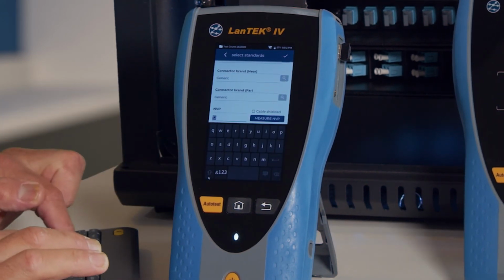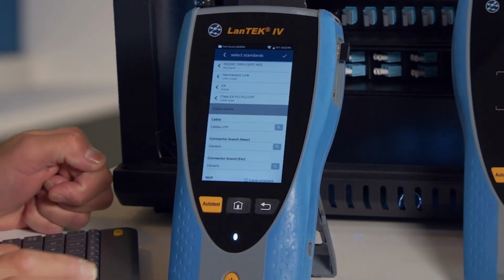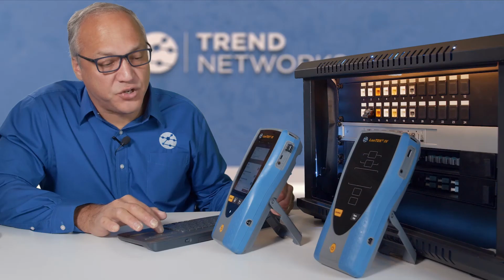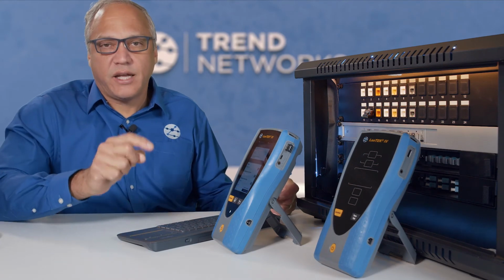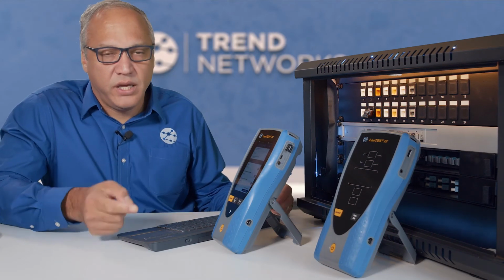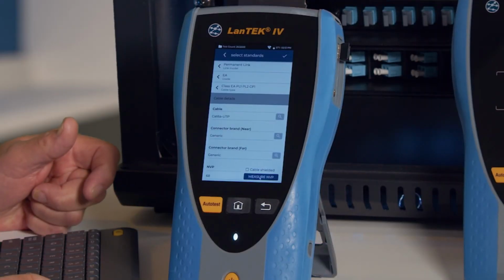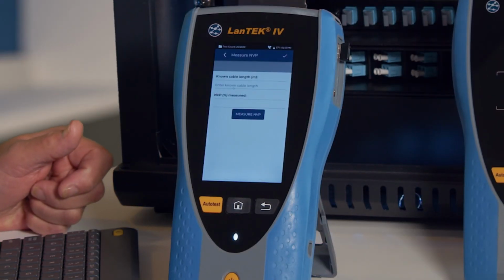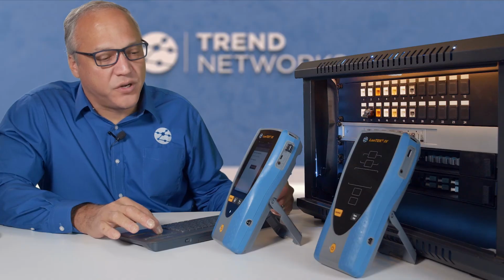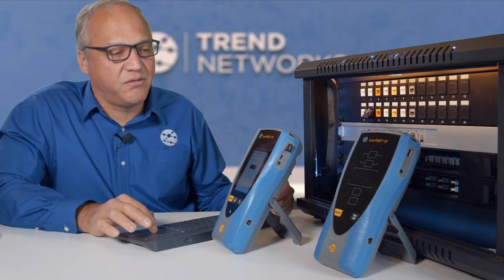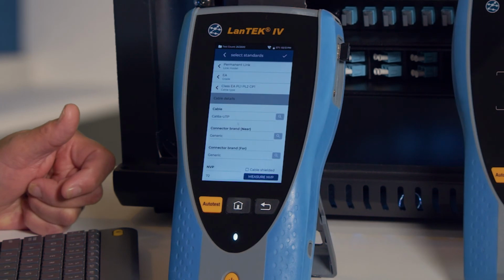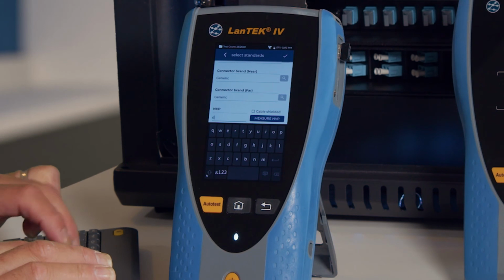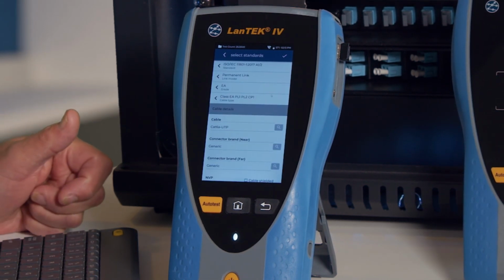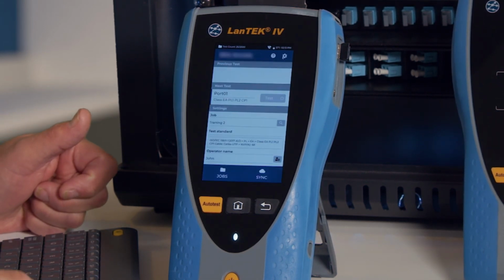So let's say it's 68% for this cable, I'll hit tab. Or I can measure the NVP by clicking that, connecting a known length of cable, hitting the measure button. So if we look at what that will do, we would connect the cable, enter the length of it, click measure, and then it will calculate the NVP and feed that back to us. But we'll just leave it at 68, enter, and hit OK. So now our configuration is shown here.